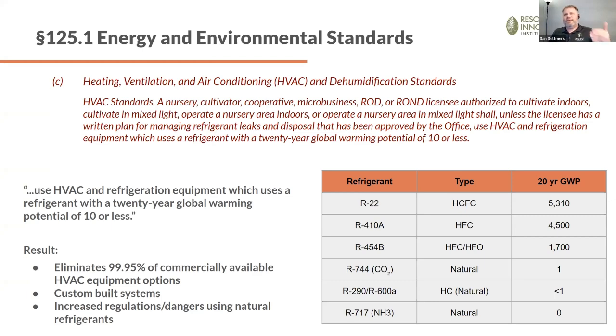Because your only option if you want to stay below 10 GWP or less is, well, R744, which is carbon dioxide; R290 and R600A, which are respectively propane and butane, kind of explosive substances; and R717, which is ammonia. I came from the ammonia industry. I love ammonia - it's a great refrigerant, extremely efficient, wonderful to the environment. I mean, for Pete's sake, it's fertilizer, but it's very toxic and it's flammable.